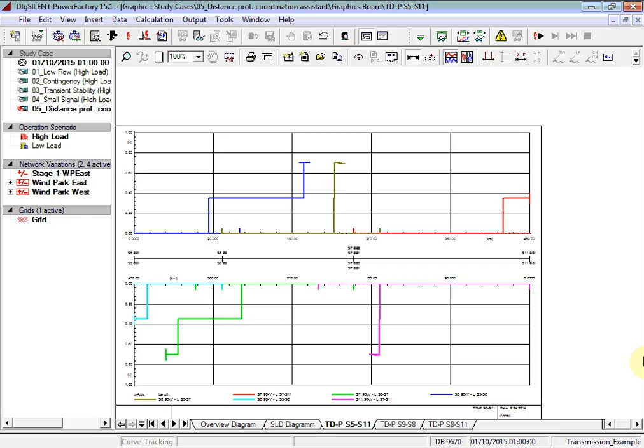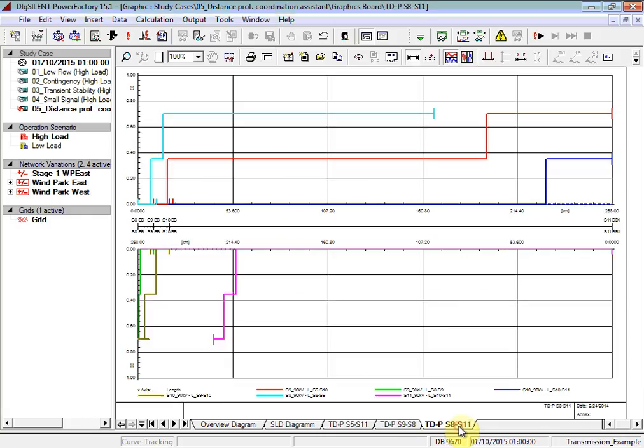You can see that 3 time distance coordination diagrams have been created. Let's focus on the time distance coordination diagram for path S8 to S11. The time distance coordination diagram illustrates distance along the x-axis and tripping time along the y-axis. The upper diagram illustrates the tripping time for power flows from the left of the diagram towards the right of the diagram, i.e. from busbar 8 in the direction of busbar 11.